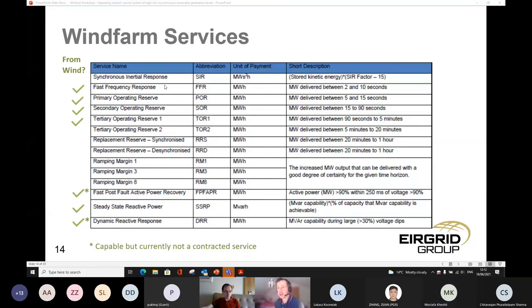I don't envisage any form of centralized switch on/off of this. The measurement needs to happen locally to achieve these very fast responses. There isn't a centrally dispatched 'deliver fast frequency response now' type of control envisaged. I think the mode is enabled or not in advance, but the actual triggering of the response is all through local measurement and activation.